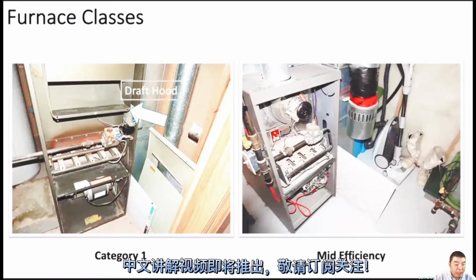Be mindful to check for cracks as well, because this is where the exhaust gas goes through before leaving through the chimney. This unit generally has the aluminum sealant. You can see here, aluminum sealant. But a long time ago, they just used sheet metal, like our ductwork system, not the aluminum. You can still see the regular sheet metal vent. But because sheet metal rusts easily, later they changed to aluminum. You can still see some sheet metal ones.